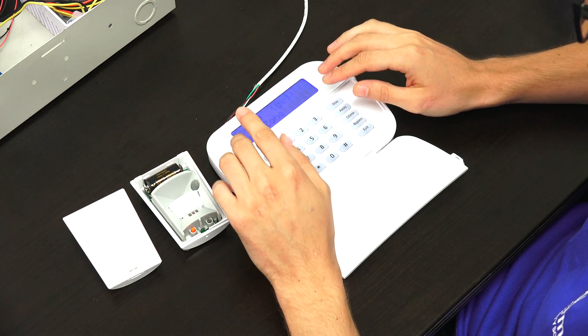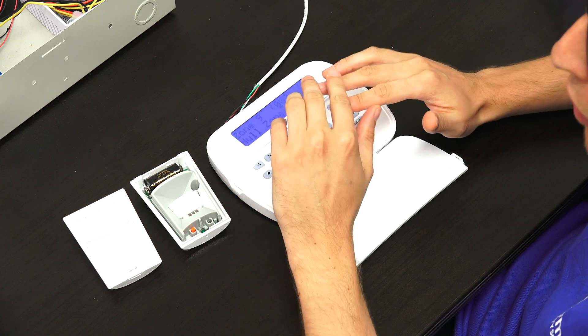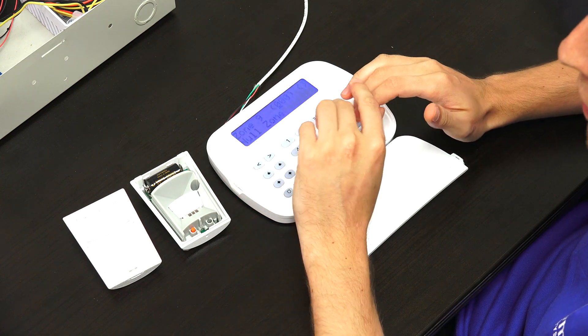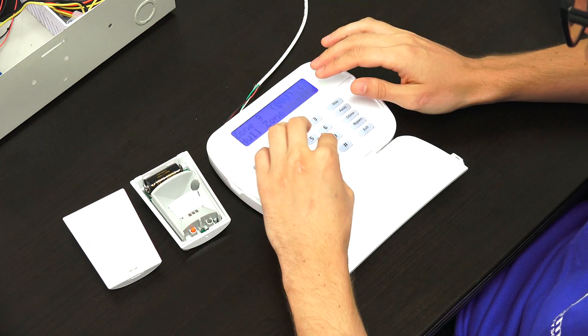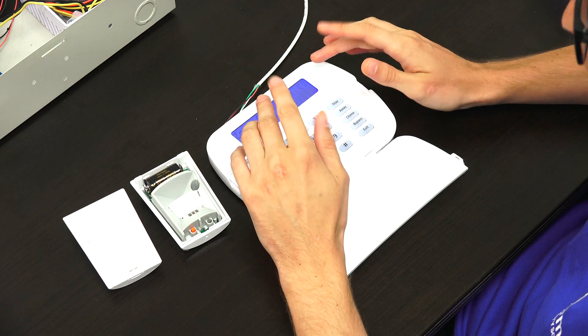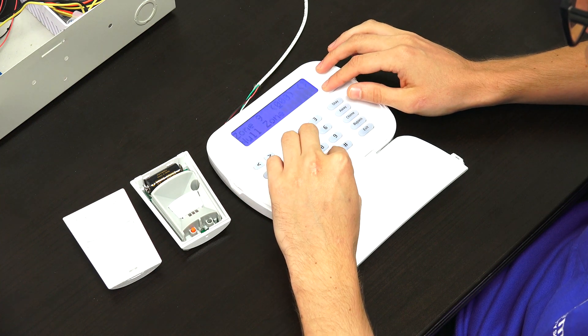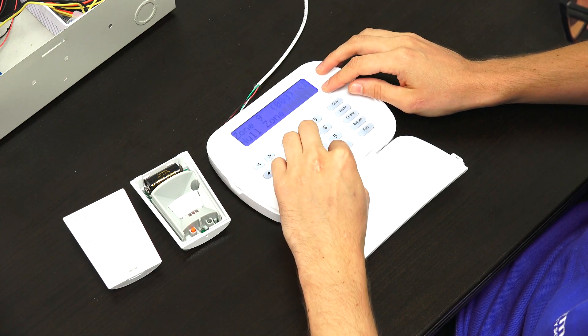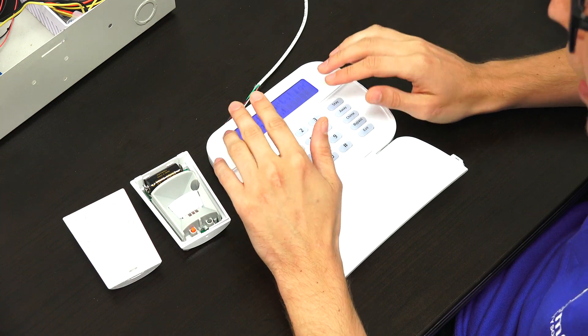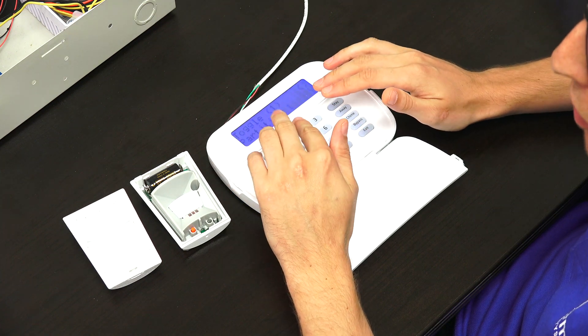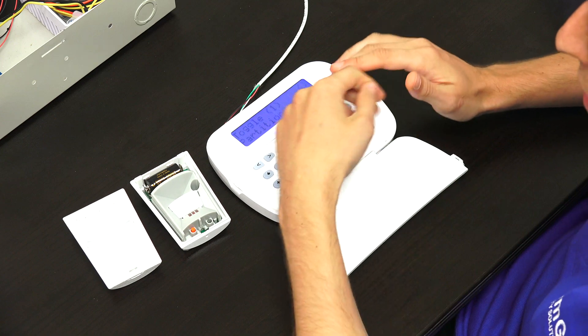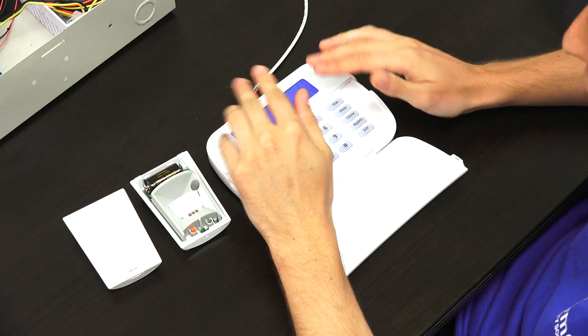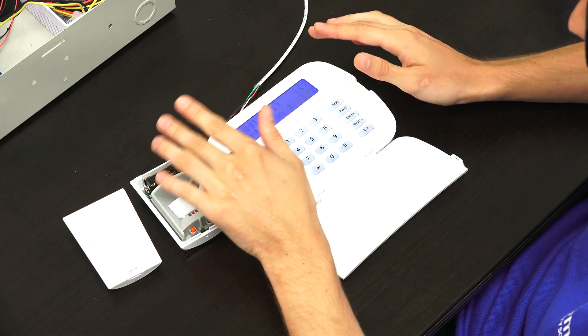And now we need to choose our zone definition. This is going to affect how the system responds when the sensor is faulted. In our case, we have a motion sensor. Let's say it's an interior motion sensor, so we'll choose 004. And remember to refer to the NEO manual if you aren't sure about a zone definition. You can find all the zone definitions listed in the manual. So find the one that works for you.